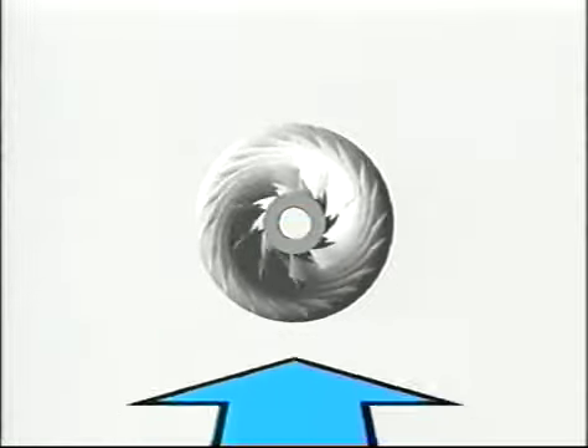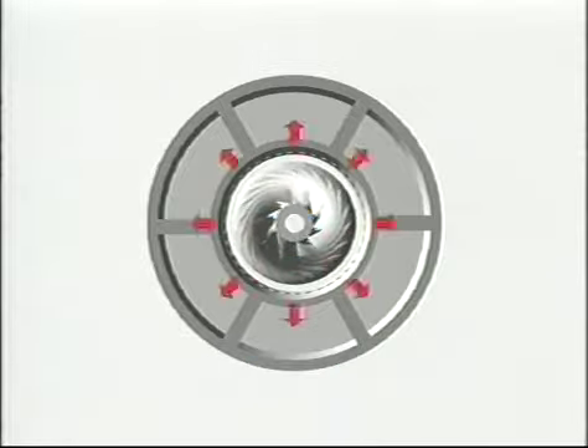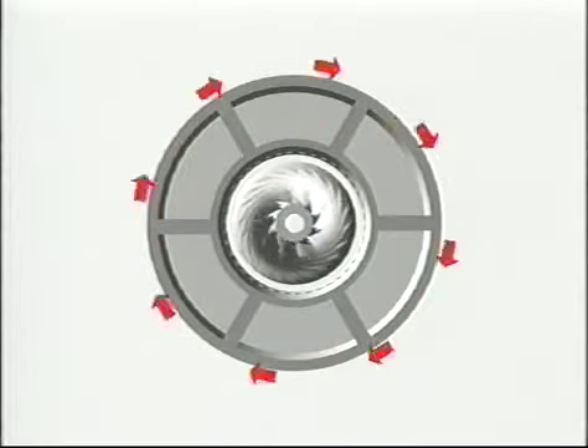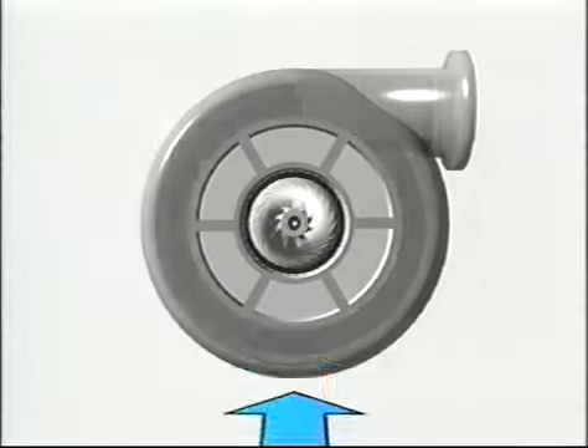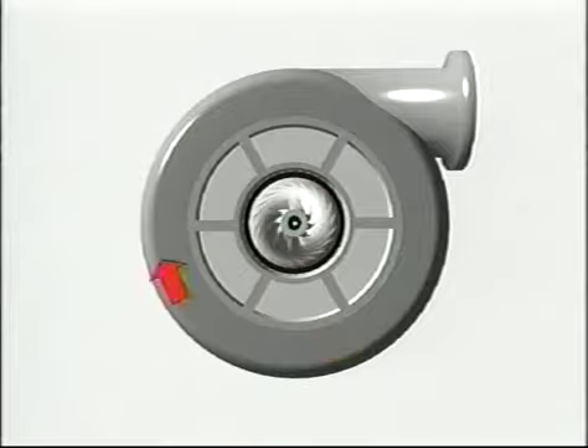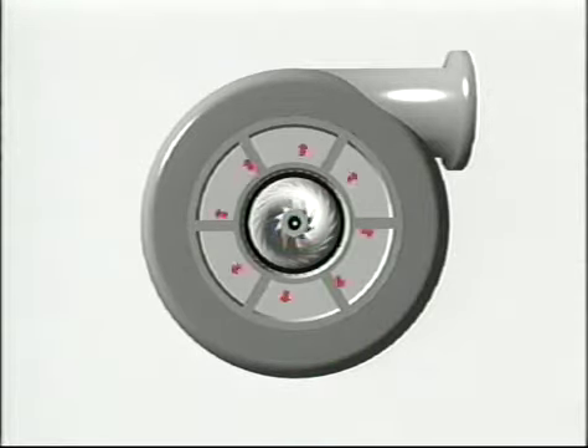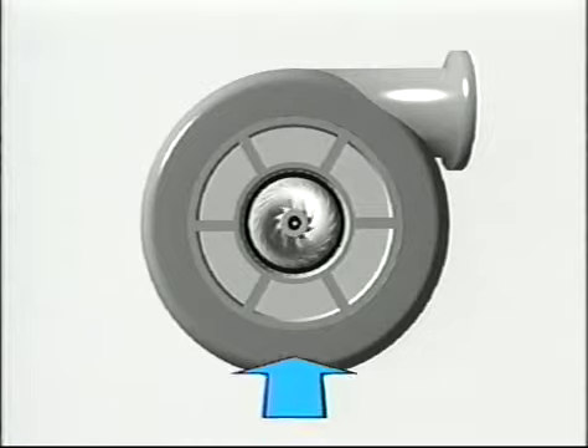However, high velocity is not high pressure. In order to get a pressure increase, or compression, the vapor must be slowed down to convert its velocity pressure to static pressure. This is accomplished in the diffuser. As the high-velocity vapor moves radially outward through the diffuser, the flow area increases, slowing the vapor and increasing the pressure. Some diffusers have vanes or pipes which change the flow direction and further slow the vapor. Finally, the volute-shaped casing collects the slow-moving high-pressure vapor from around the diffuser and conveys it to the discharge connection of the compressor.